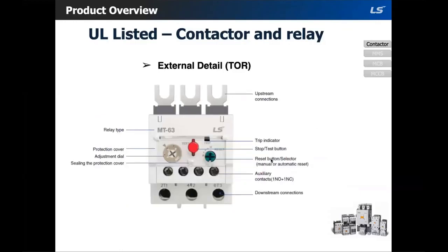Let's look at the overload now. We have adjustable current dial, trip indicator, reset selector, and a stop test button on our overload. And our overloads come with one normally open and one normally closed aux contact as standard.